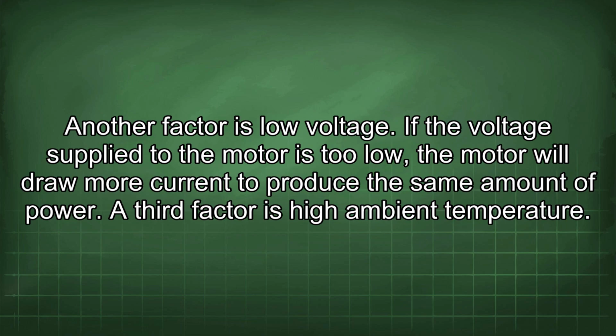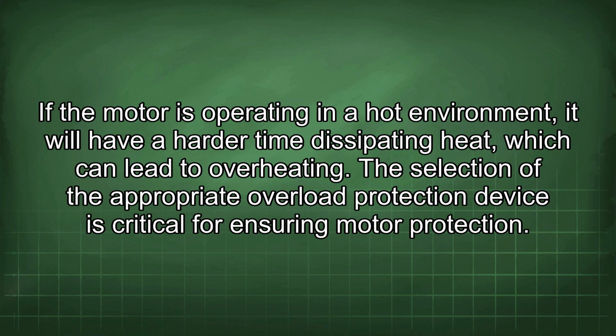If the voltage supplied to the motor is too low, the motor will draw more current to produce the same amount of power. A third factor is high ambient temperature. If the motor is operating in a hot environment, it will have a harder time dissipating heat, which can lead to overheating. The selection of the appropriate overload protection device is critical for ensuring motor protection.